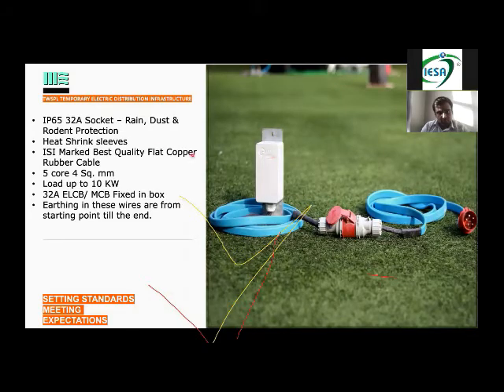These are the heat shrink sleeves which I spoke about. I told you that the sockets can be IP67 or 65, but when you're connecting your cables inside the socket, there is still a small gap left. So we cover it with a heat shrink sleeve, so that even a droplet of water doesn't go inside, because there are live wires connected to it. So, 5-core 4 mm cable suitable for a 32 amp socket. Inside this, there could be a 32 amp MCB or an ELCB or both, or an RCBO.